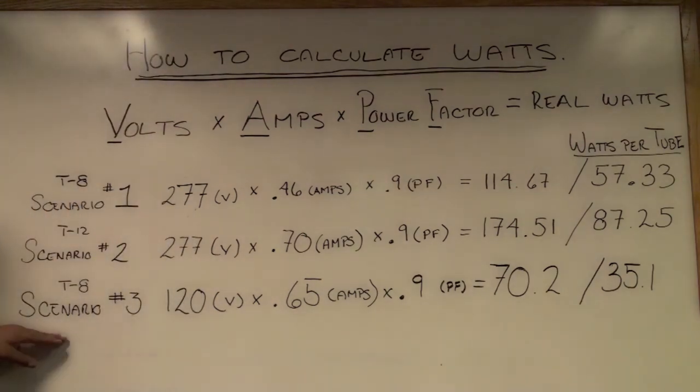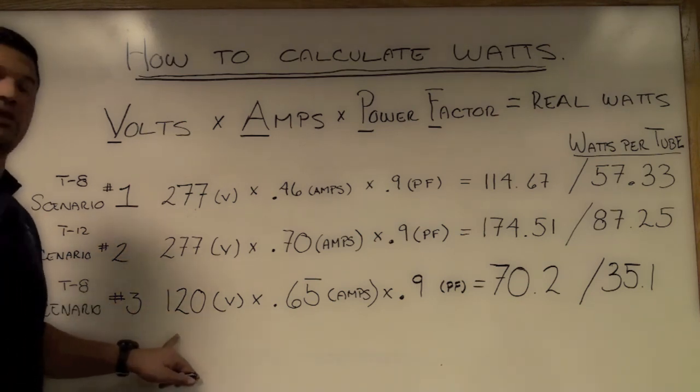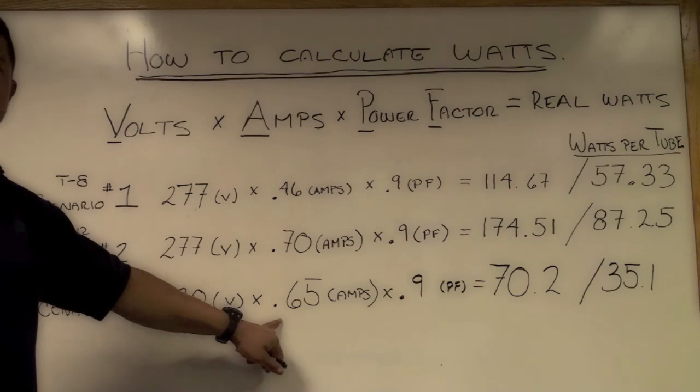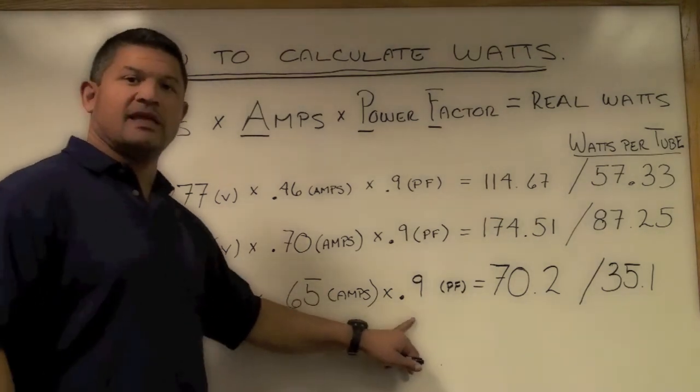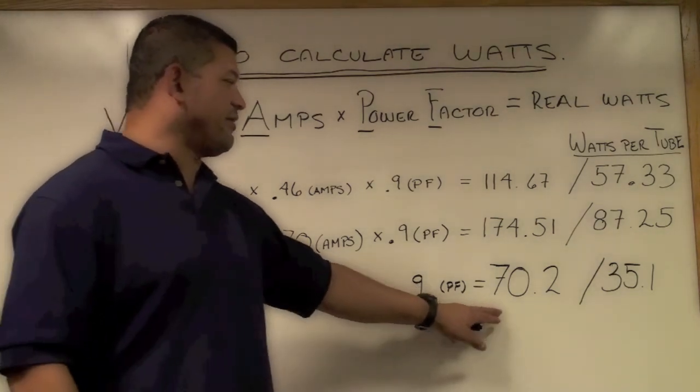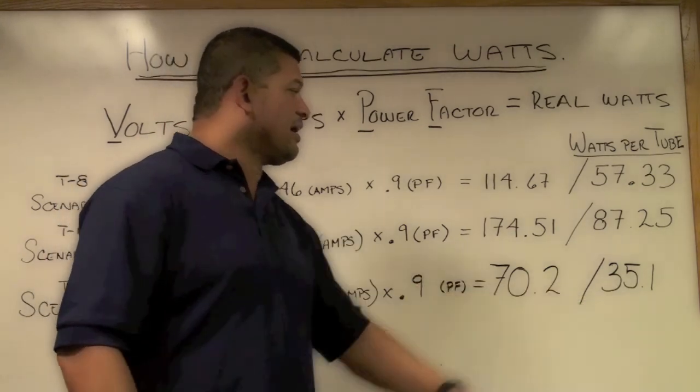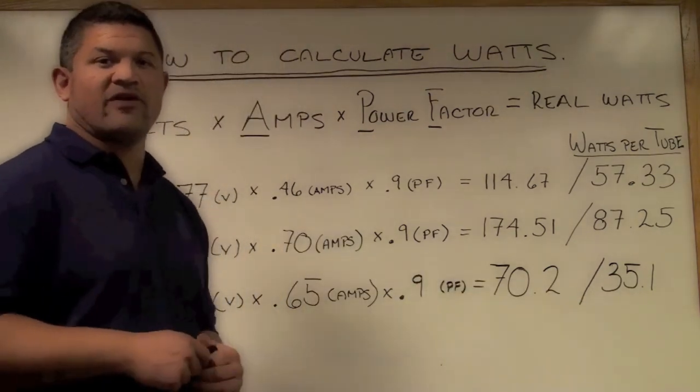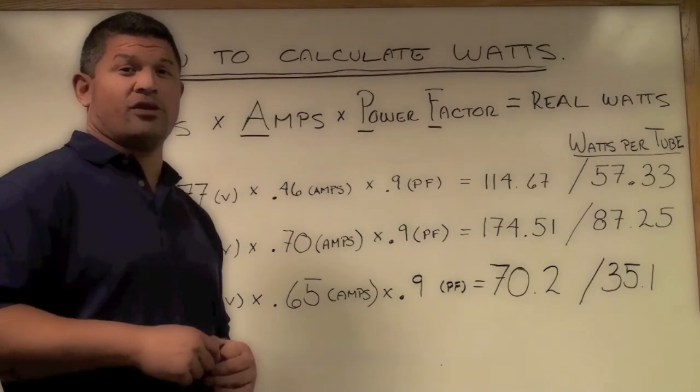In addition, scenario number three we have a T8 unit with 120 volts per unit, 0.65 on the amperage, 0.9 once again as a standard default brings it to 70.2 and dividing it by the two tubes that you have is 35.1 watts per unit.